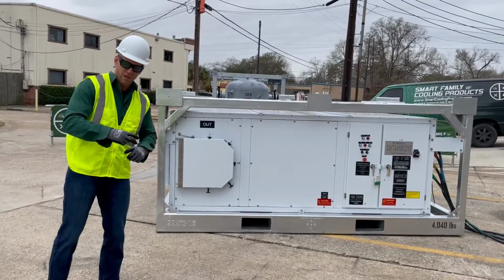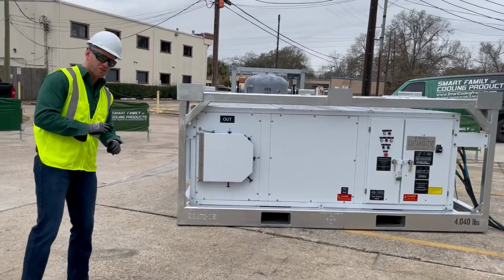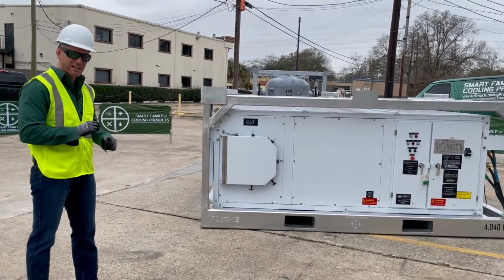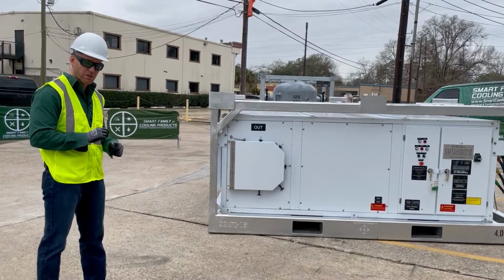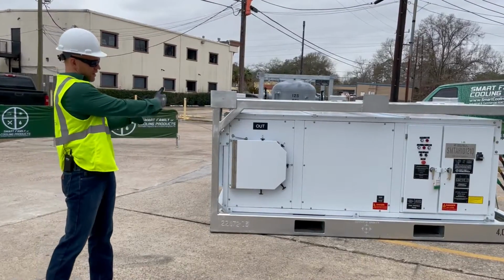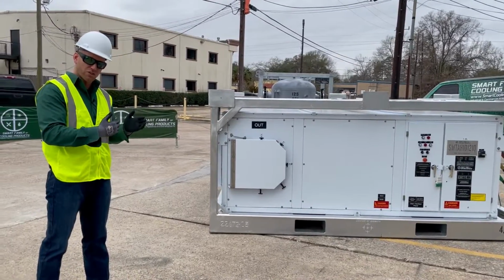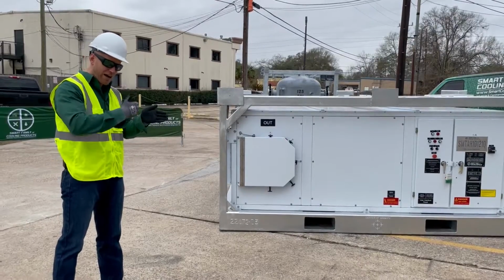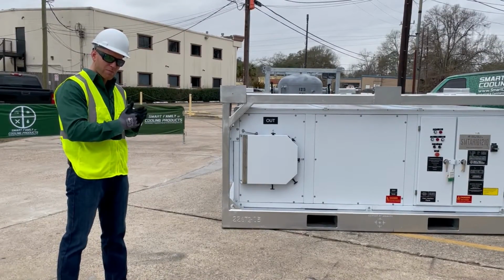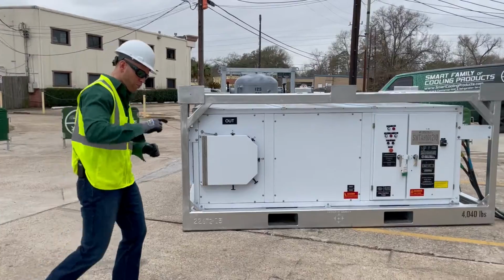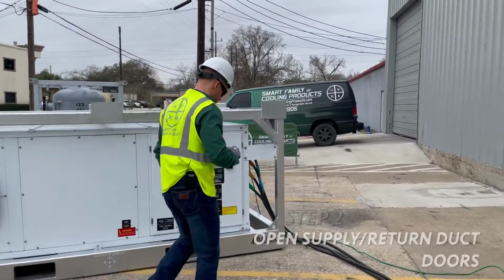We've done that. Step number two, we need to make sure that this air handler has a clear and clean path for the airflow to get through the machine. So to allow airflow to go through the machine, we need to make sure that our inlets are open and our outlets are open. So follow me now as we walk around the package and let's go open up our inlet connections.